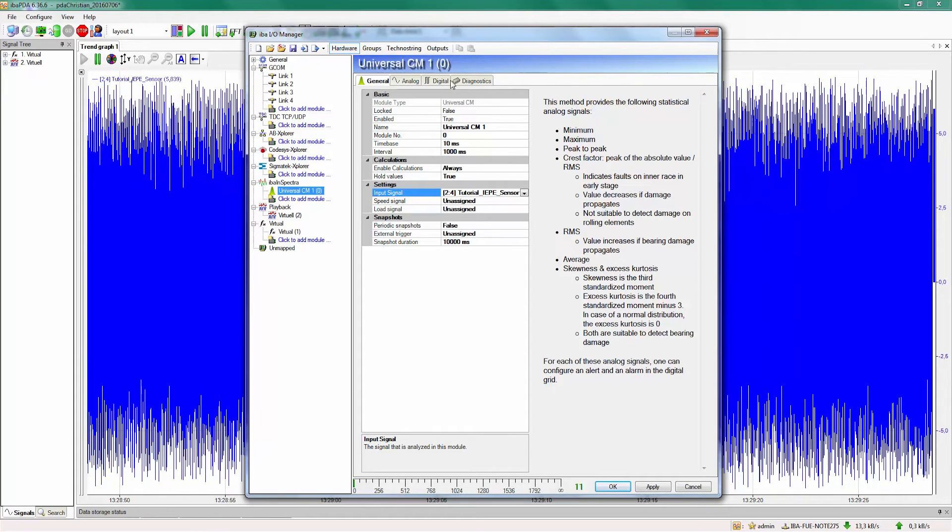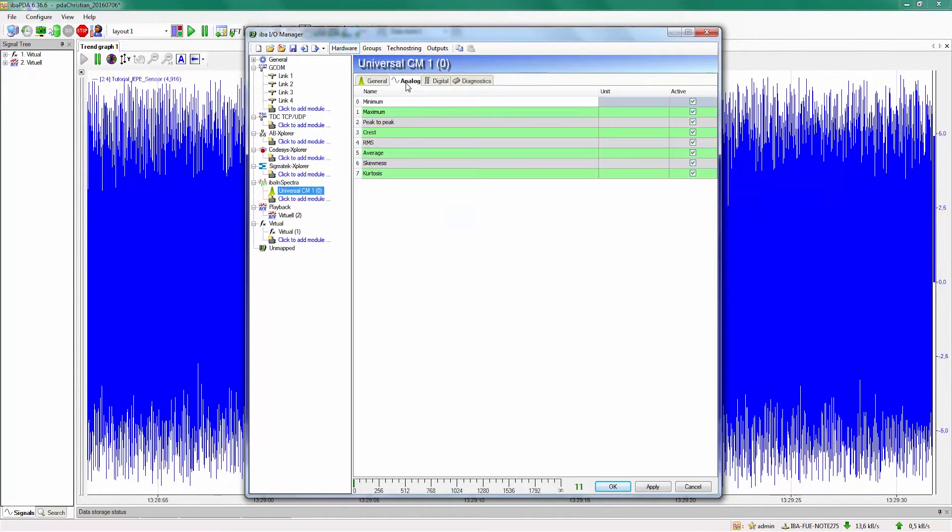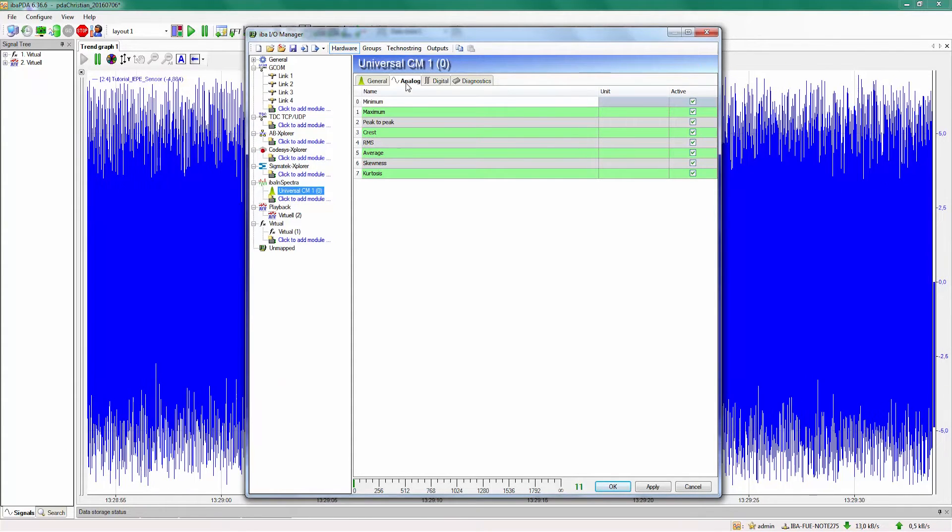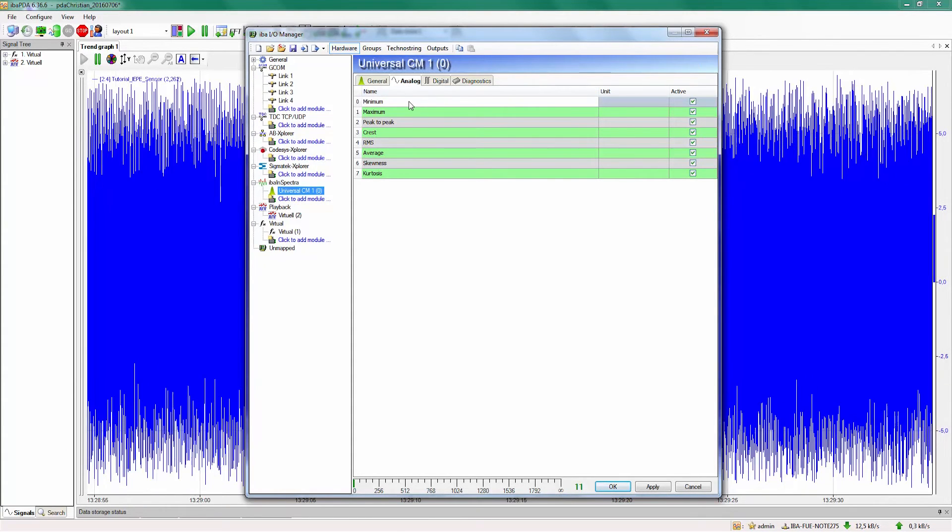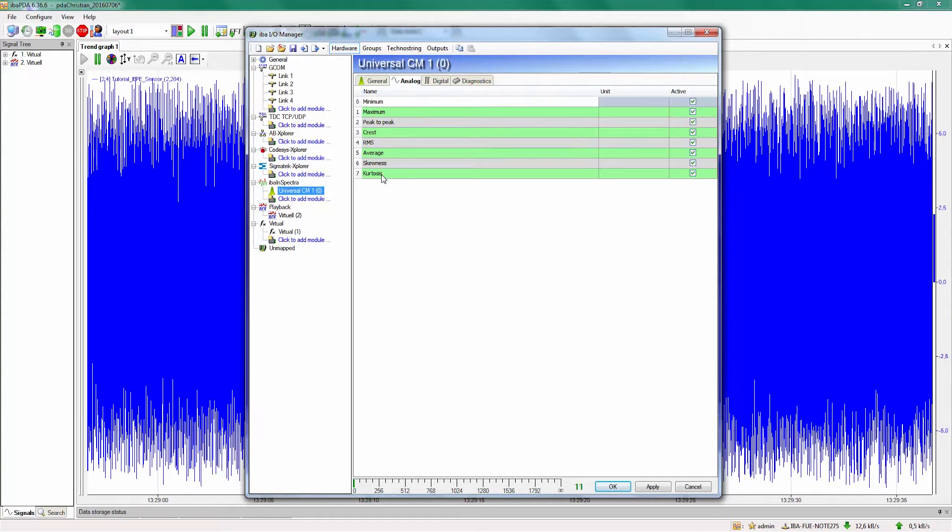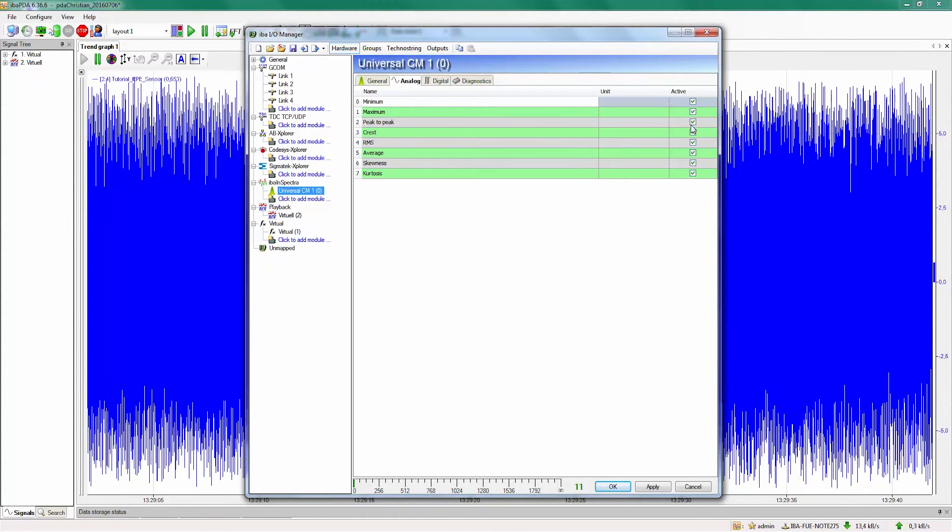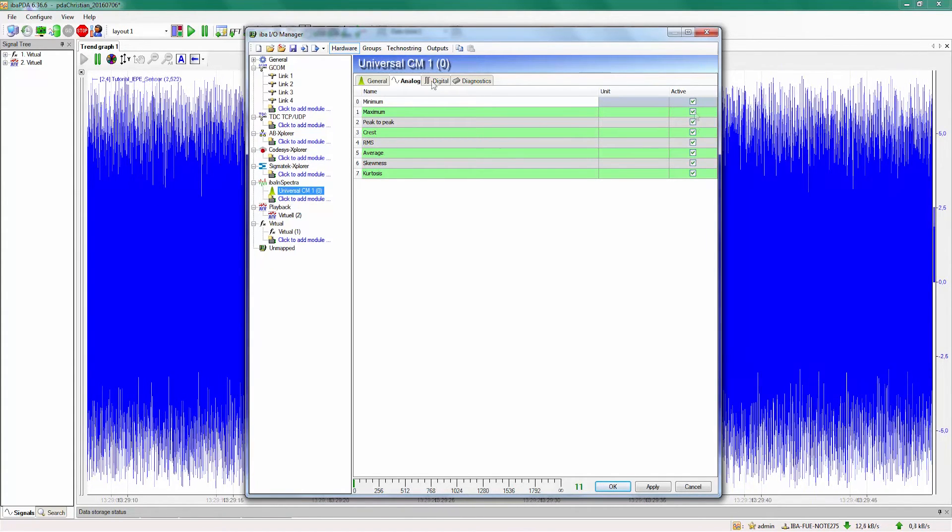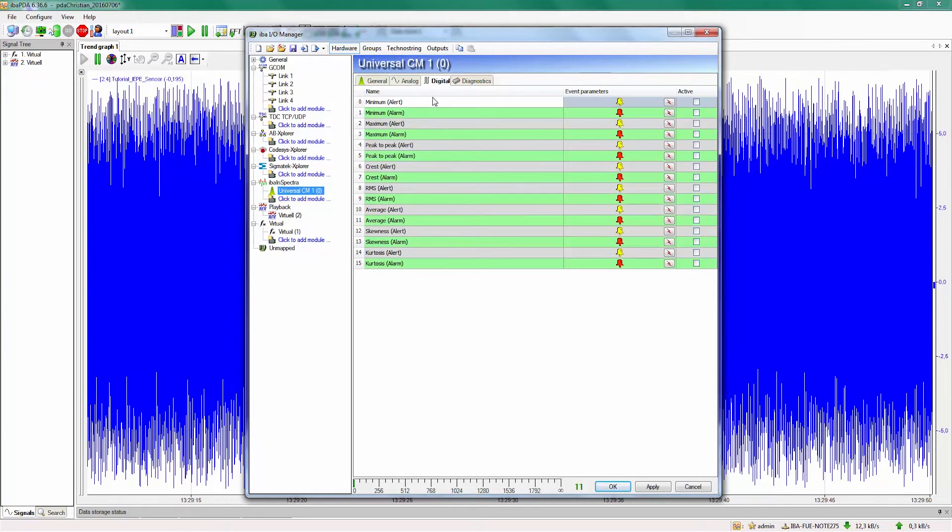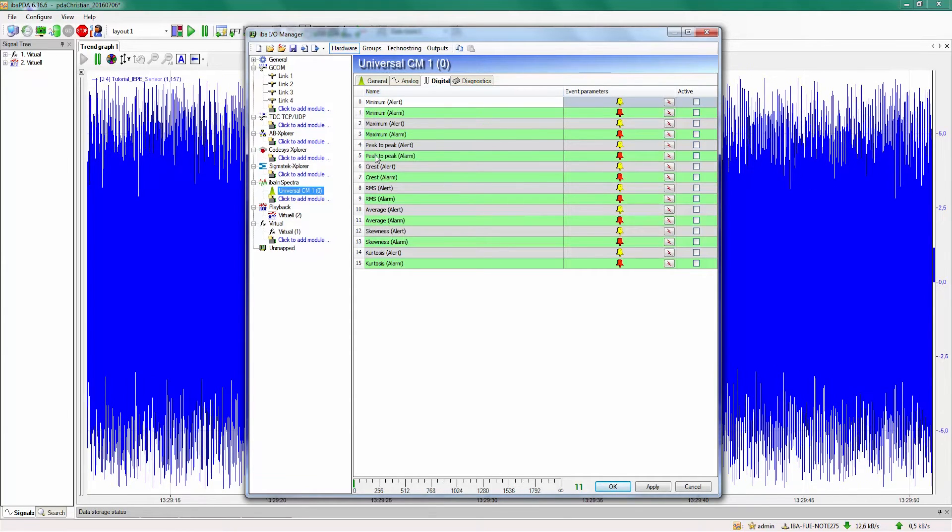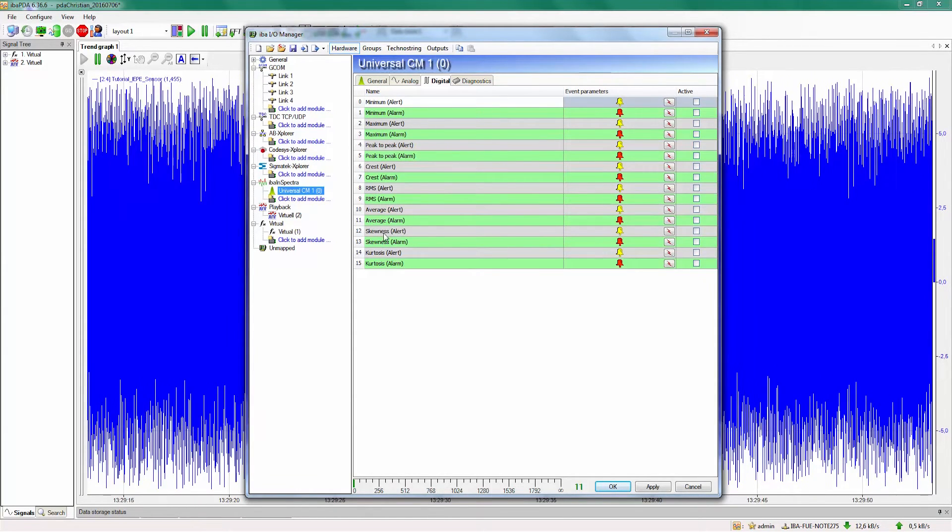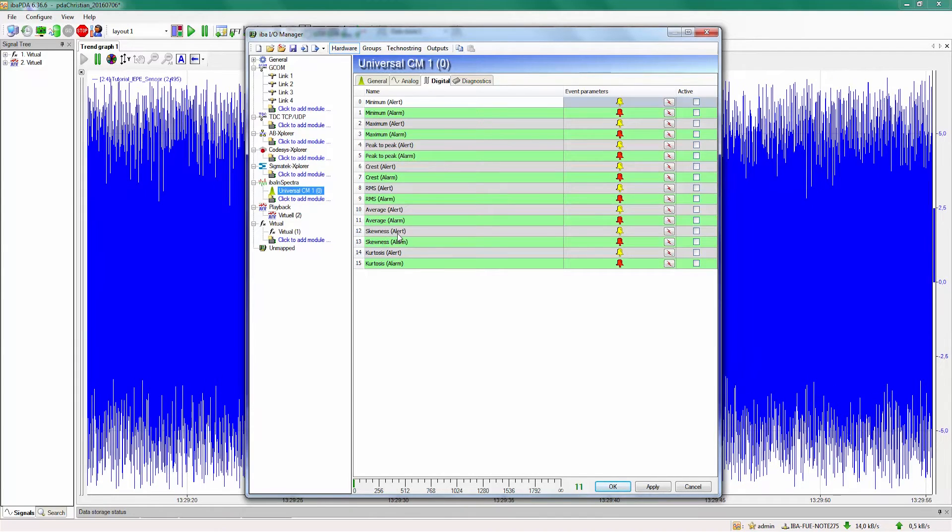When we now enter the analog signals of this module we see that all these values can be calculated. If one of these values is not needed we can deactivate or deselect it on the right side. But most important are the digital signals. Here we can now configure a warning, an alert or an alarm for each of these signals.